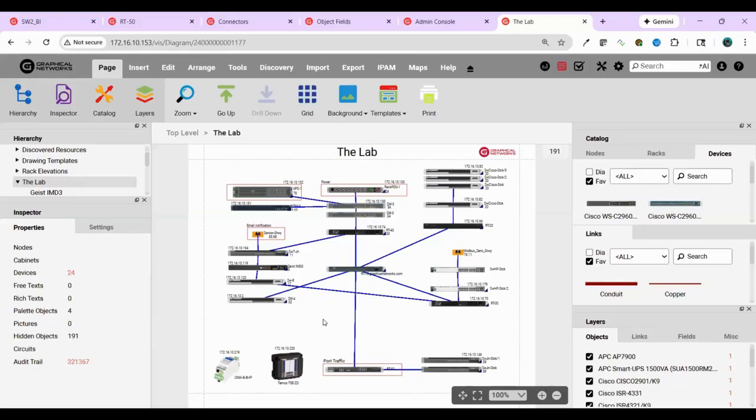Yeah, and we're vendor agnostic, right? It's just about SNMP. That's correct. So it's not so much about a vendor. It's about are they SNMP enabled? Versions 2 and 3 typically are what's used, and do they provide OIDs, do they provide data for you to monitor? Not everybody does. Sometimes you have to buy a certain model type, a little bit higher end, to get some of those features and functionality.